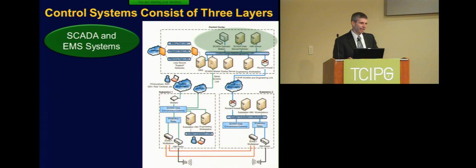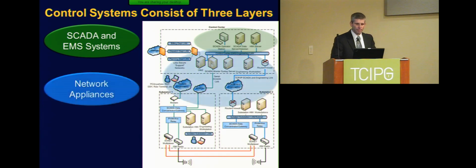There may be some connection to the billing department, the dispatch department, and maybe the planning and operations side, depending on how things are set up. But ideally they're segmented and segregated from the SCADA network above. Below the SCADA we have what I'll refer to as network appliances - switches, routers, front-end processors for modem banks. They go out to various substations to collect data, issue operation commands, or pull in volts and vars.